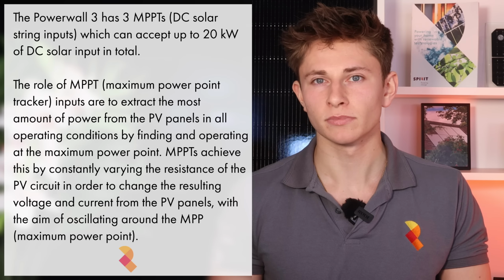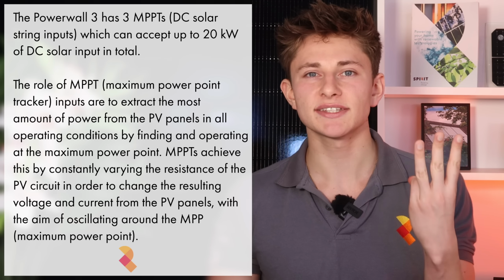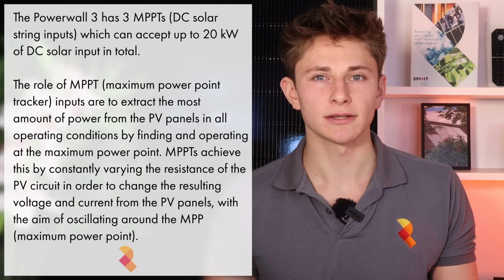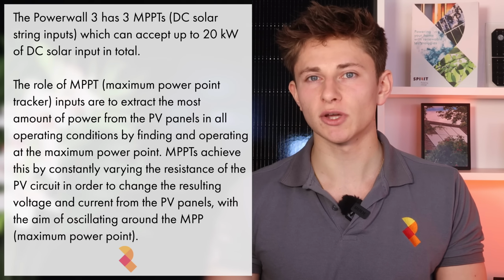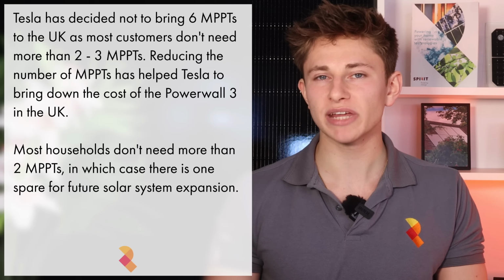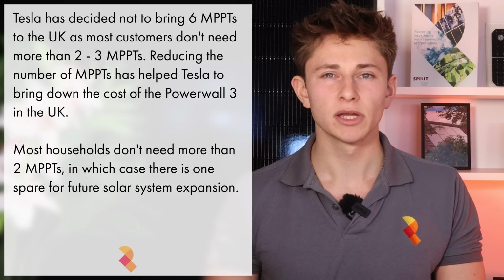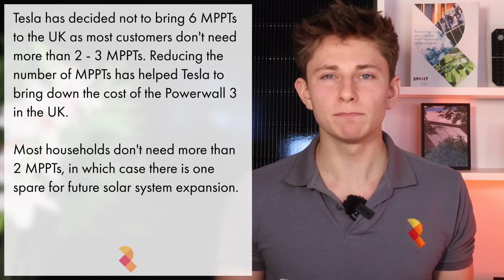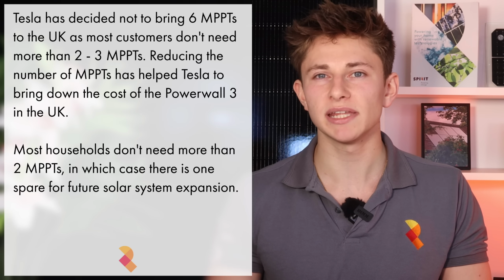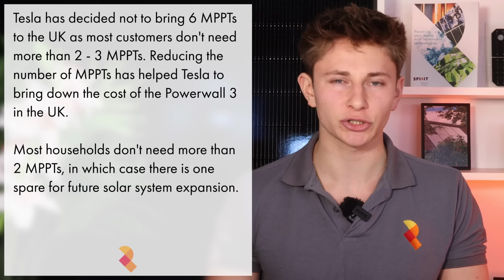That time period isn't specified by Tesla, however it's expected to be able to output more than its continuous 11.04 kilowatts for about 10 seconds to provide resilience during surge events. The Powerwall 3 inverter has 3 solar string inputs, or MPPTs, and can accept up to 20 kilowatts of solar DC input power. The American version of Powerwall 3 actually has 6 MPPTs, however Tesla felt that 3 was enough for the majority of households in the UK. Which is true, most houses don't really need more than 2 MPPTs and will usually end up leaving 1 spare for future solar system expansion.